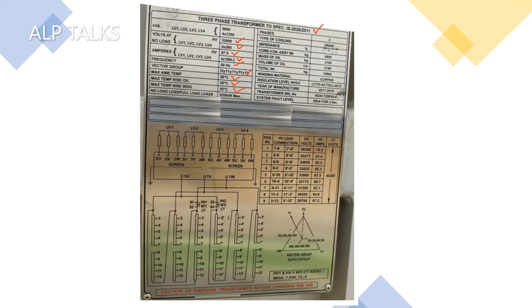This is as per IS. Now, no load loss and load loss — this is a common trend in solar power transformers: 5 and 50 kW. Generally 0.1% and 1% are the losses. Some people will say together 1%; in that case 0.1% and 0.9% will be the no load and load loss contribution. This is a 3 phase transformer.